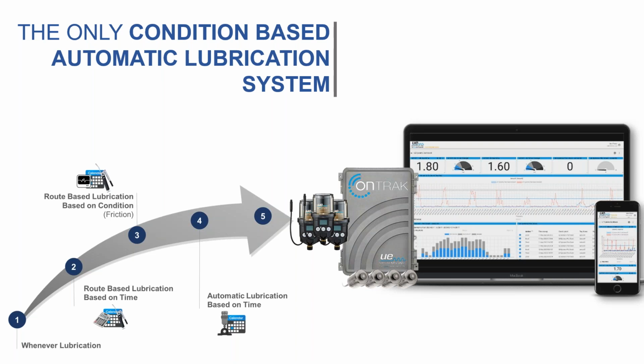And then 3 and 4 really came out at the same time. So when we look at condition-based lubrication, it is products like our ultrasound, our grease caddies, our 10s, 15,000s, where you essentially use the ultrasound to determine when and how much grease is required. So you're listening to that bearing based on the friction of the bearing, which has proven very, very successful over the years. Now, at the same time, the onset of automatic lubrication, so single point lubricators or distribution systems with a progressive distribution block in it, came out.